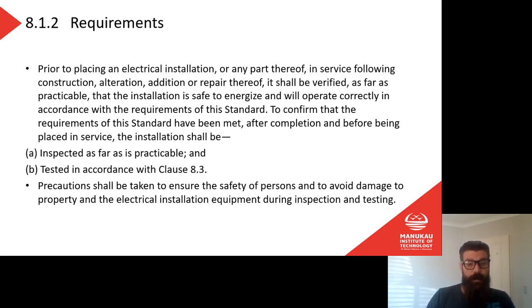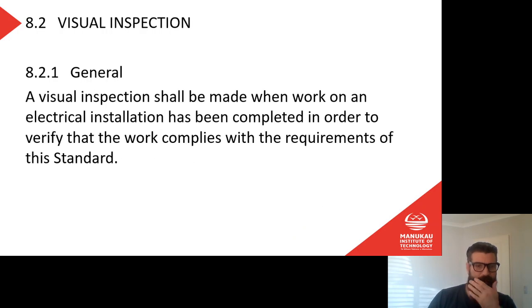Hopefully, if they're not, an example might be if one of the gib stoppers stuck a nail through one of our cables, something like that while we weren't there. Hopefully we pick that up when we're testing. But again, it does not require us to rip all the walls off so that we can prove it, because that would not be practicable. And B there says tested in accordance with clause 8.3. So before we turn anything on, we have to test in accordance with section 8.3. Precaution should be taken to ensure the safety of persons and to avoid damage to property and the electrical installation equipment during inspection and testing. So while we're testing, we shouldn't do anything dangerous.